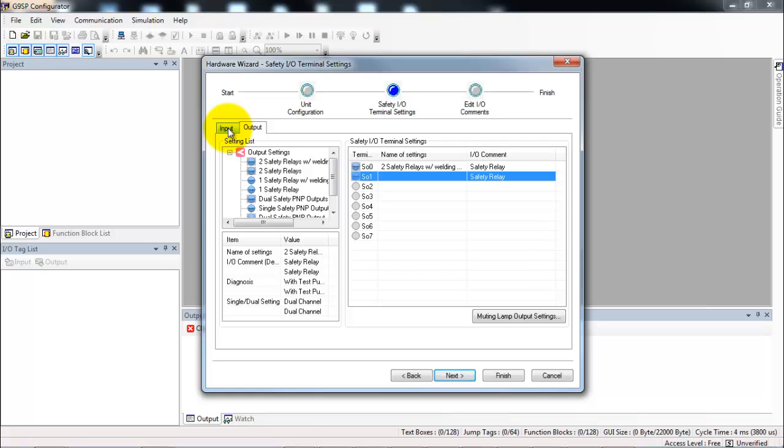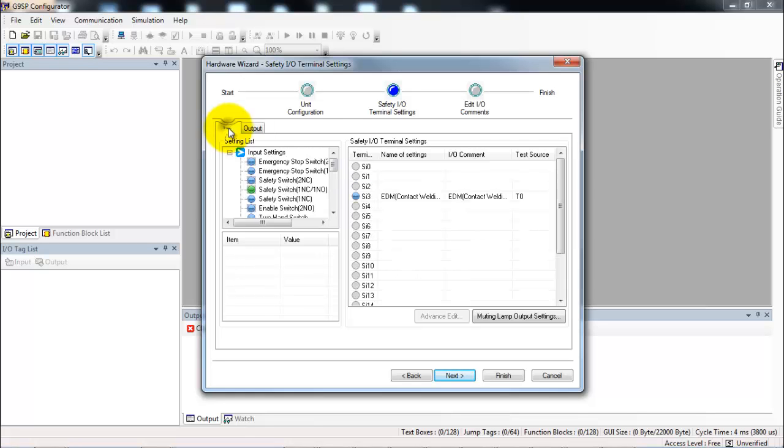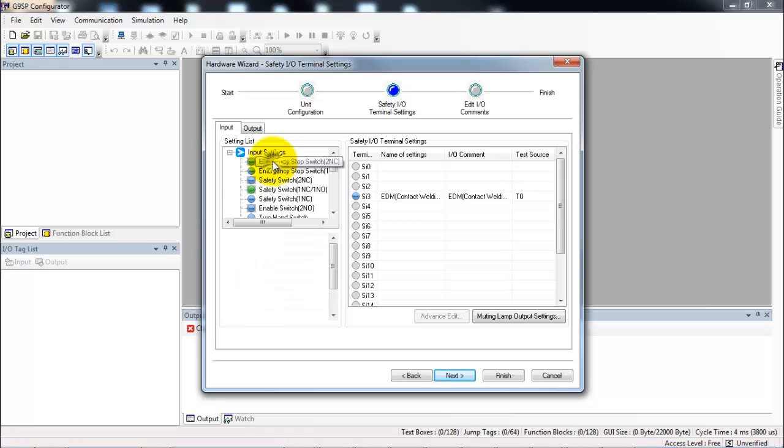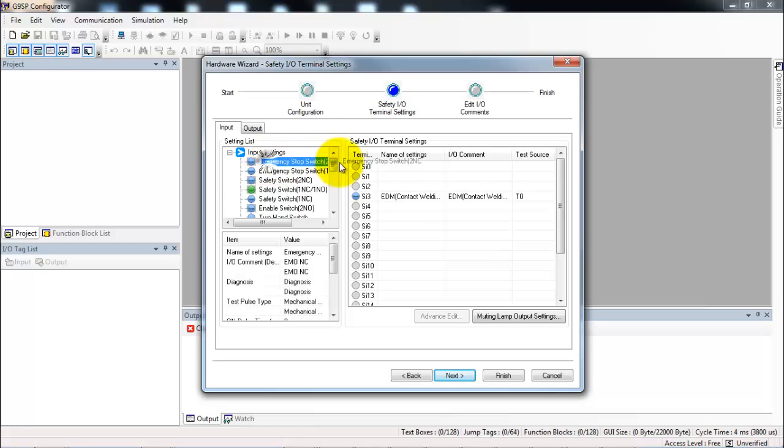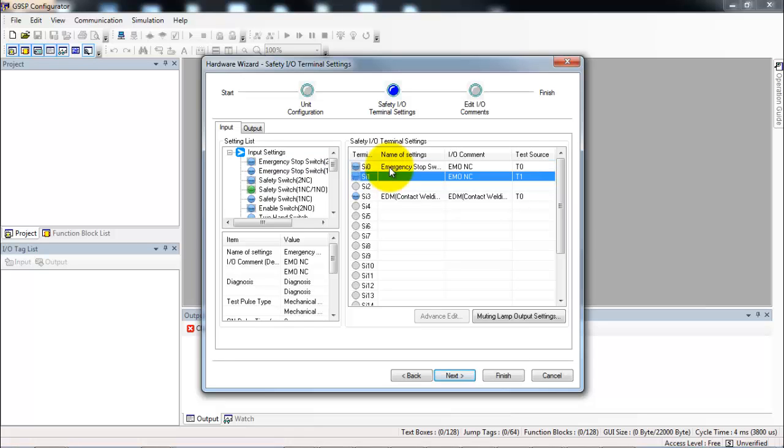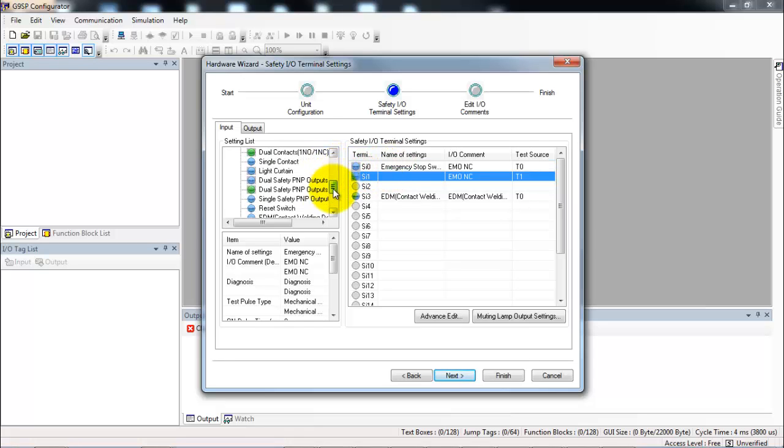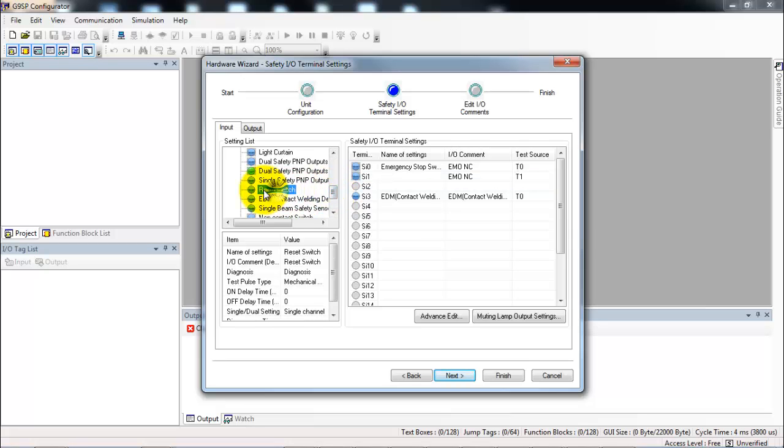We're done with the outputs, so now we go to the input tab. Here I need to add in the e-stop switch with two normally closed contacts. I put that on top of input 0 and 1. And a little further down the list of options here there's a reset switch, and I'll drag and drop that onto safety input 2.